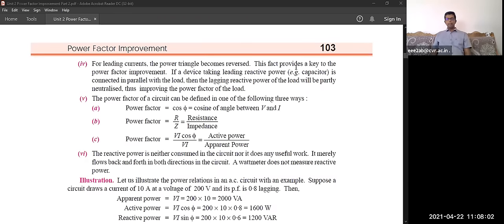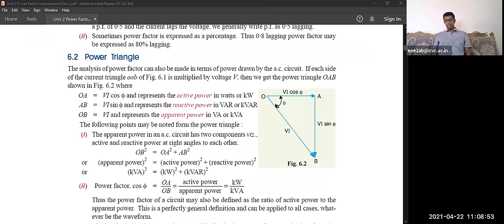For leading currents, the power triangle reverses. This provides the key to power factor improvement. If a device taking leading reactive power — for example, a capacitor — is connected in parallel with the load, then the lagging power factor of the load will be partially neutralized, thus improving the power factor. The voltage and current will come closer to the same axis, improving the overall power factor of the circuit.